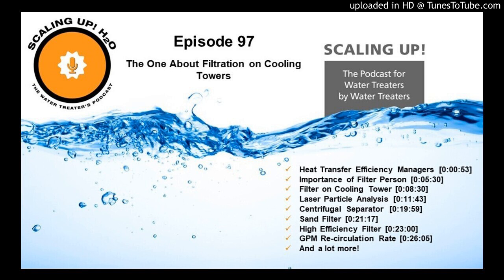An example of that: I had a cogen plant in Hartford, you can tell by my Boston accent, where every year when they cleaned out the sump, they were up to their knees in mud and sludge, and they hated it. Barrels and barrels of stuff to remove. I told them I thought you would reduce the amount of sedimentation by putting a filter on there, but you never know exactly how much, because if there are a lot of heavy solids coming in the air, which there shouldn't be, then you could have sump deposition anyway.